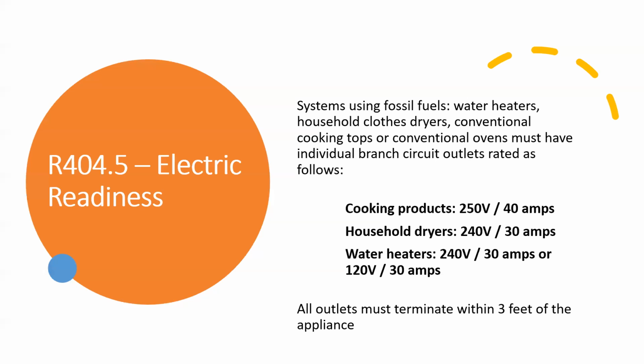Another one here that's bringing up a lot of concern and conversations is systems using fossil fuels: water heaters, household clothes dryers, conventional cooking tops, conventional ovens must have individual branch circuit outlets rated as follows. So cooking, household dryers, water heaters all need to have electricity tied in behind it if they're using a gas appliance. Here it gives the rating of 250 volts with 40 amps behind cooking appliances, 240 volts with 30 amps behind household dryers, and then 240 volt with 30 amps or 120 volt with 30 amps for water heaters. And all outlets must terminate within 3 feet of the appliance.